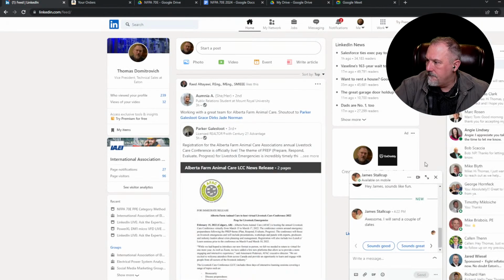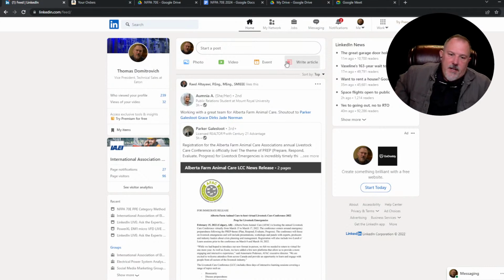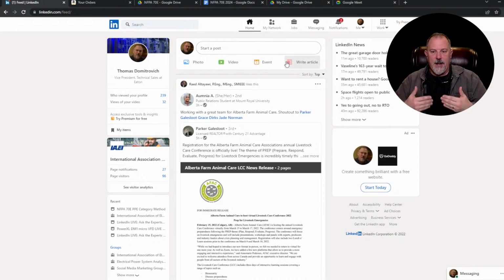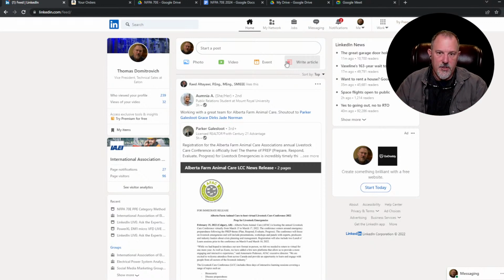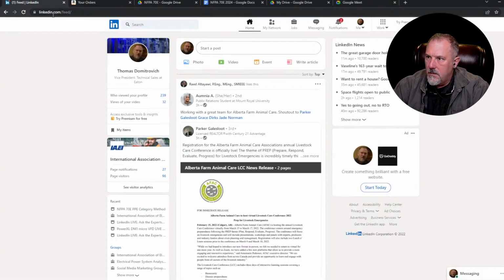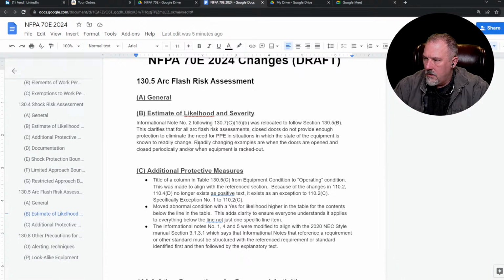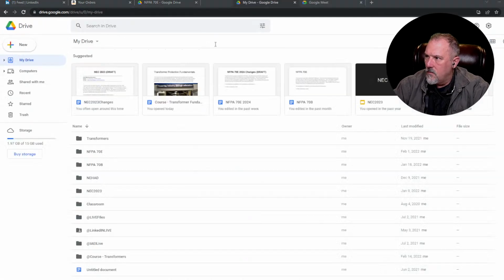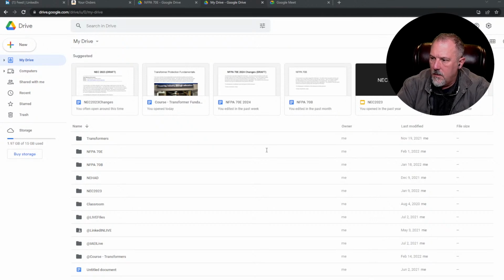Yeah. And maybe what they're talking about too is, if you have a medium voltage breaker, if you rack a breaker out with the door closed, if something happens during that activity, the door is not going to provide you a barrier. So, okay, all right. But where does that fall? I suppose it falls into 130.5. Estimate of likelihood and severity. So the likelihood of something happening is increased when you are doing something that readily changes the state of the equipment. That's what he's trying to make the point on.